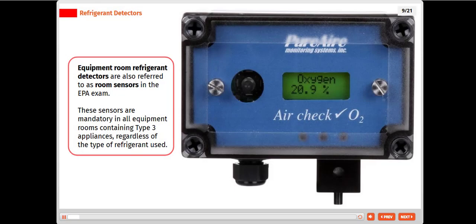Equipment room refrigerant detectors are also referred to as room sensors in the EPA exam. These sensors are mandatory in all equipment rooms containing Type 3 appliances, regardless of the type of refrigerant used.